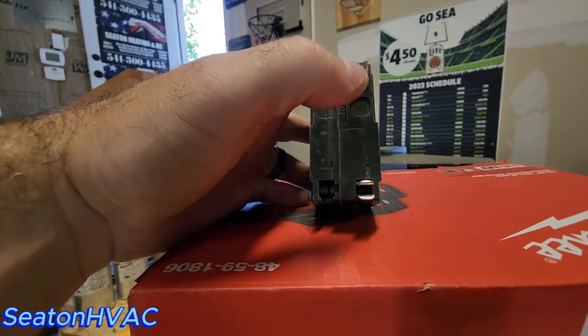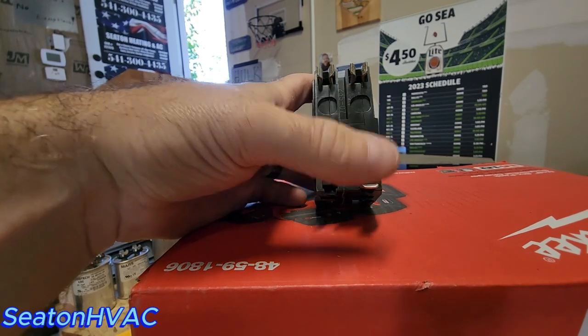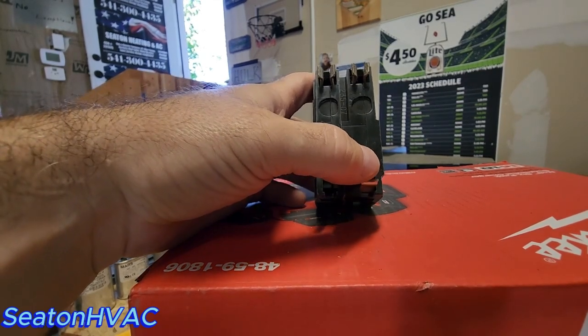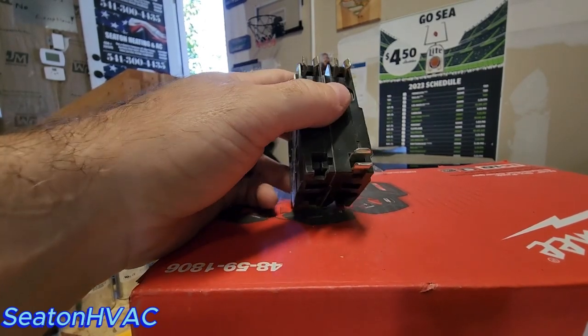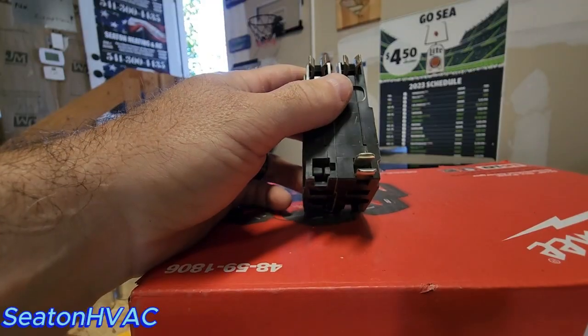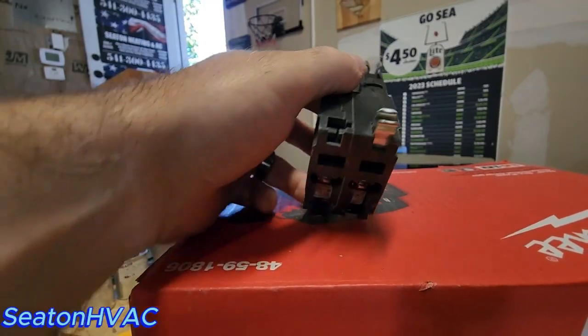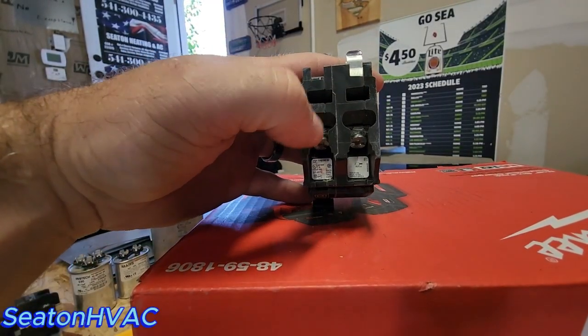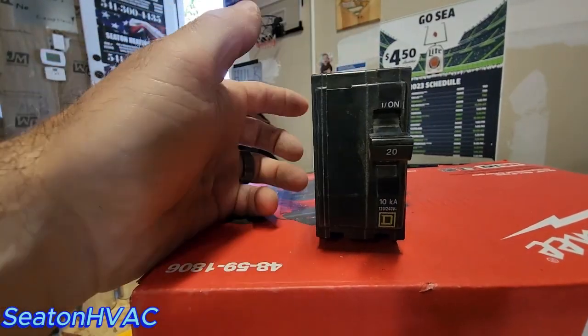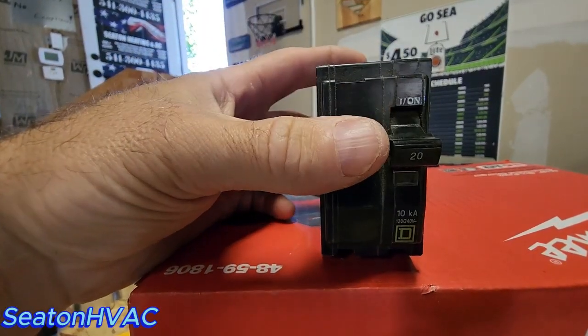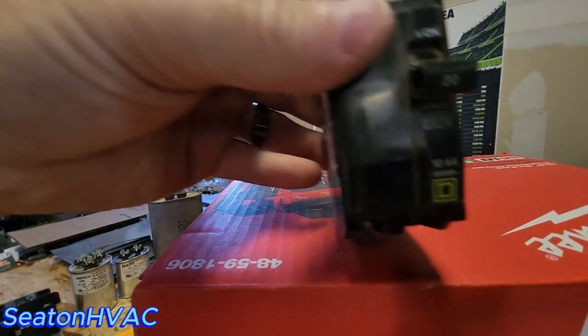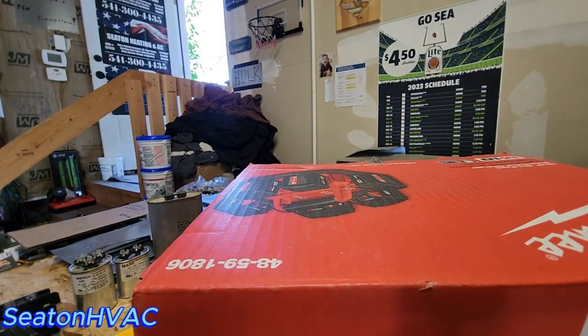So this is your 240 coming in. This actually is just to mount it in the panel. There's no power here, obviously. That's just the way they clip onto the bus bar on the panel. But same thing, 120 volts, 120 volts, 120 volts, 120 volts to your panel. So another type of 240 volt breaker. And then I'll show you the last one, the simplest of them all.